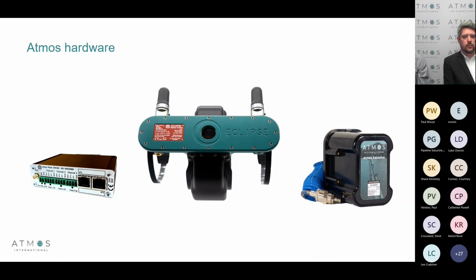The reason we use edge processing, getting the internal circuit board to do most of the work, is the issue of communication. Some of these water pipelines are in remote locations where 4G isn't easily available, and we want to keep the cost of transmitting data down. So the device only transmits when it suspects a potential leak, and that data gets sent to a portal where we can analyze it effectively.